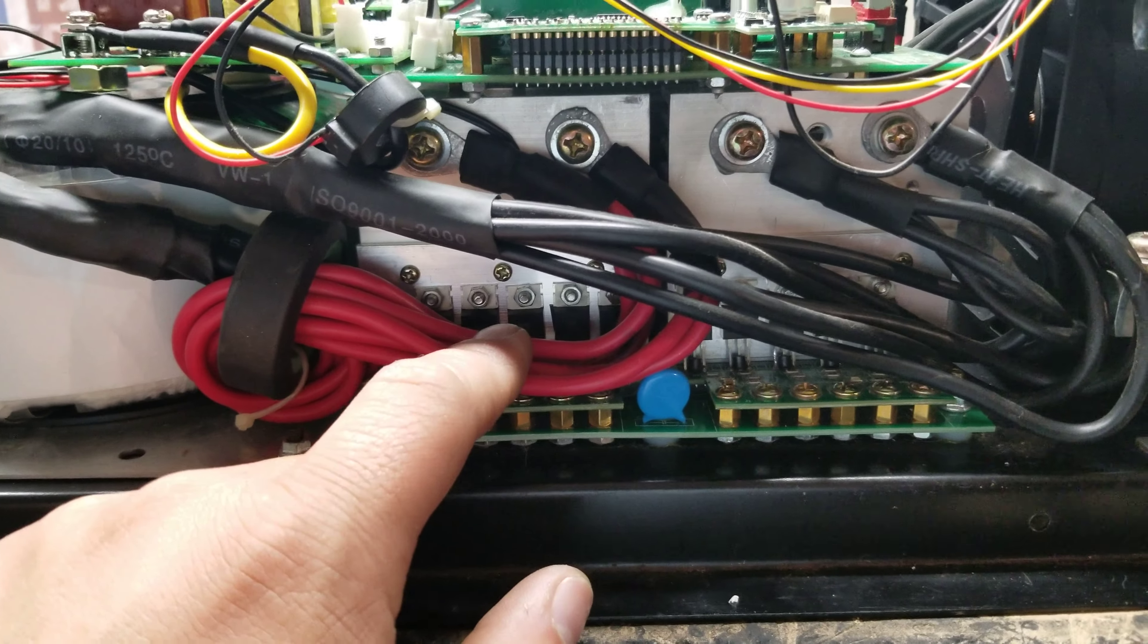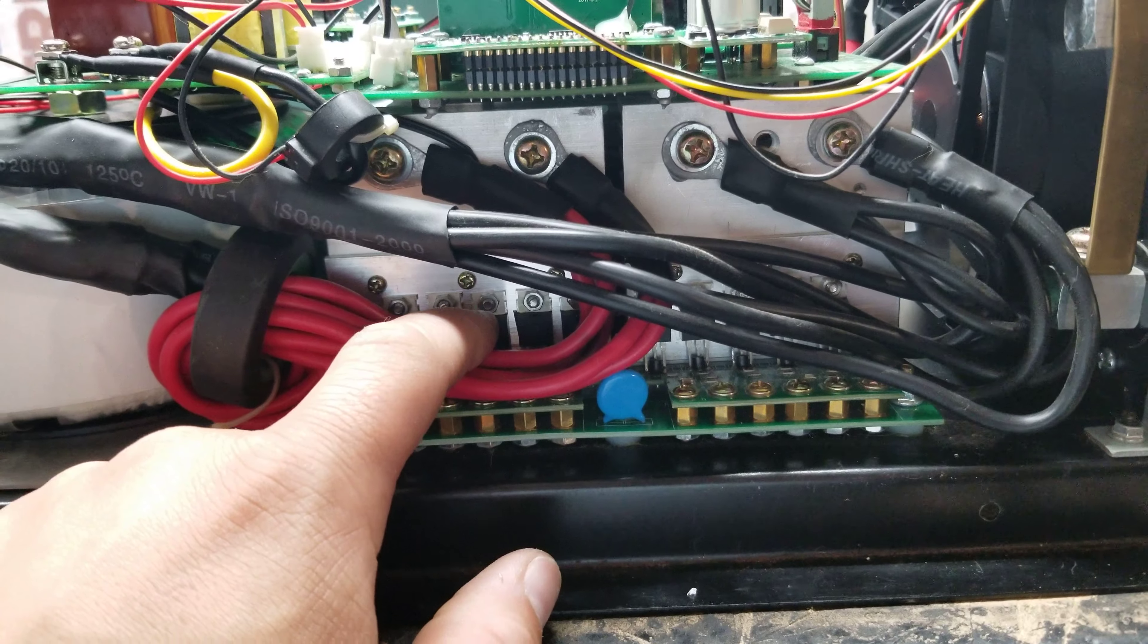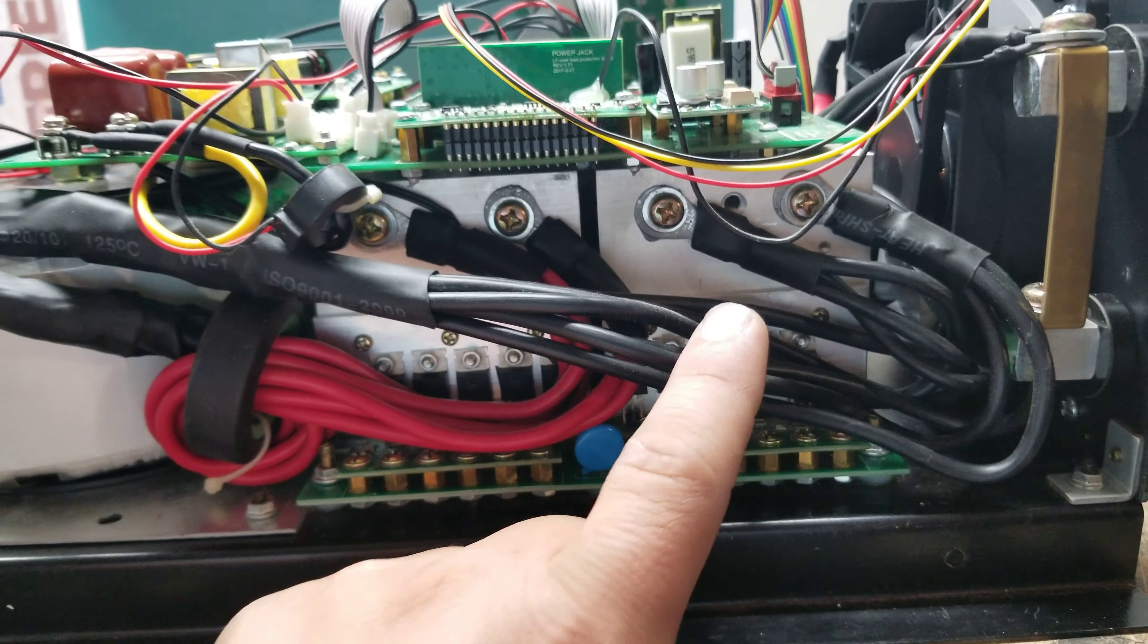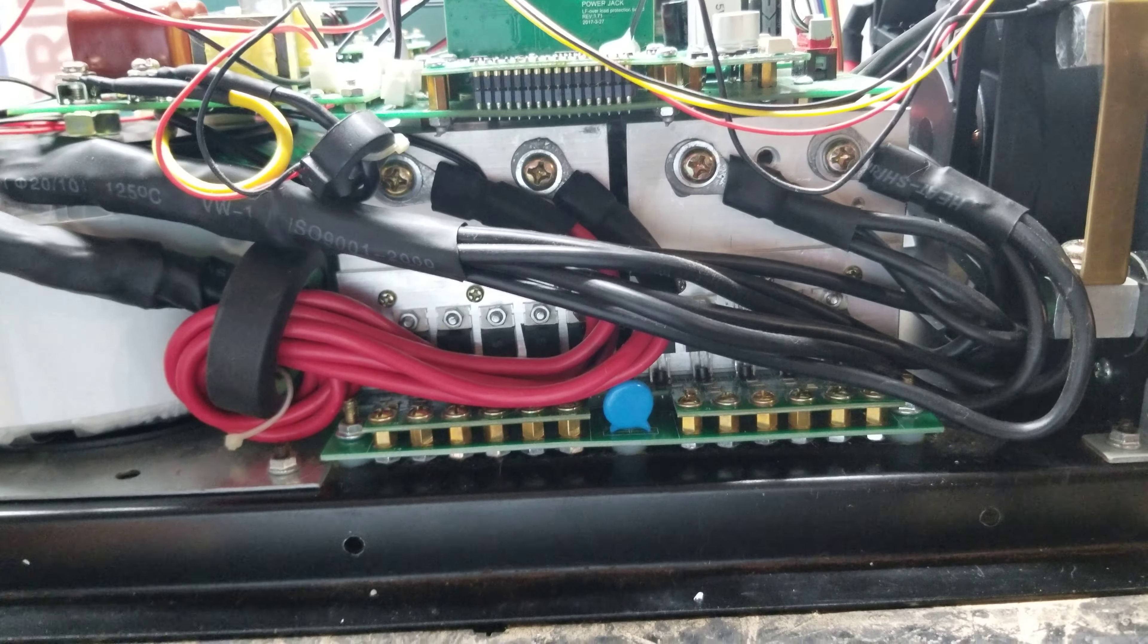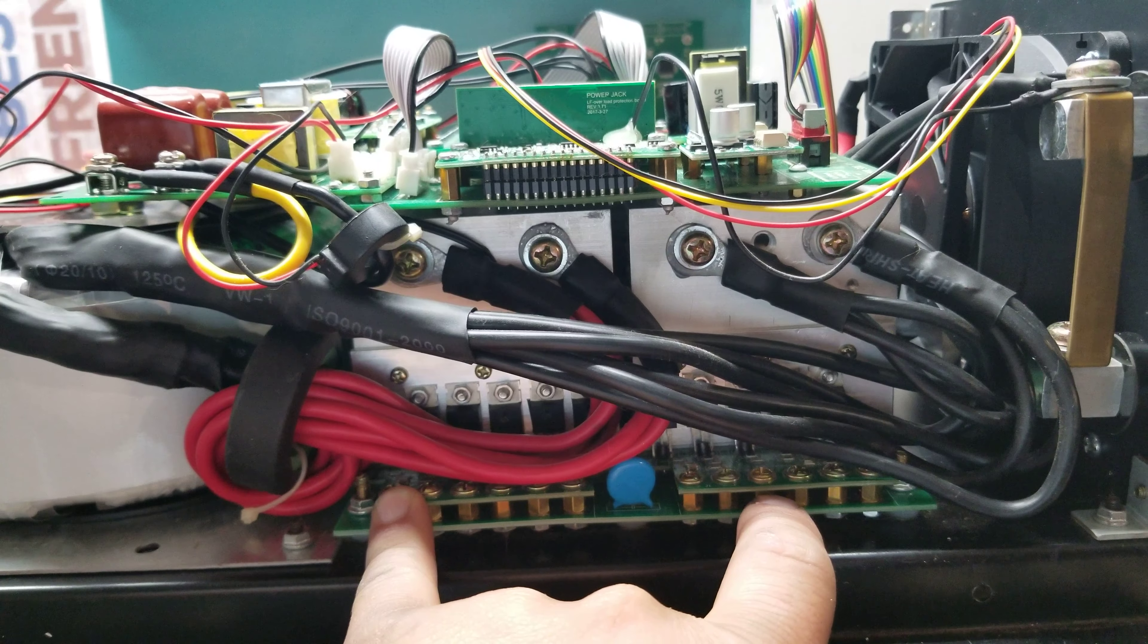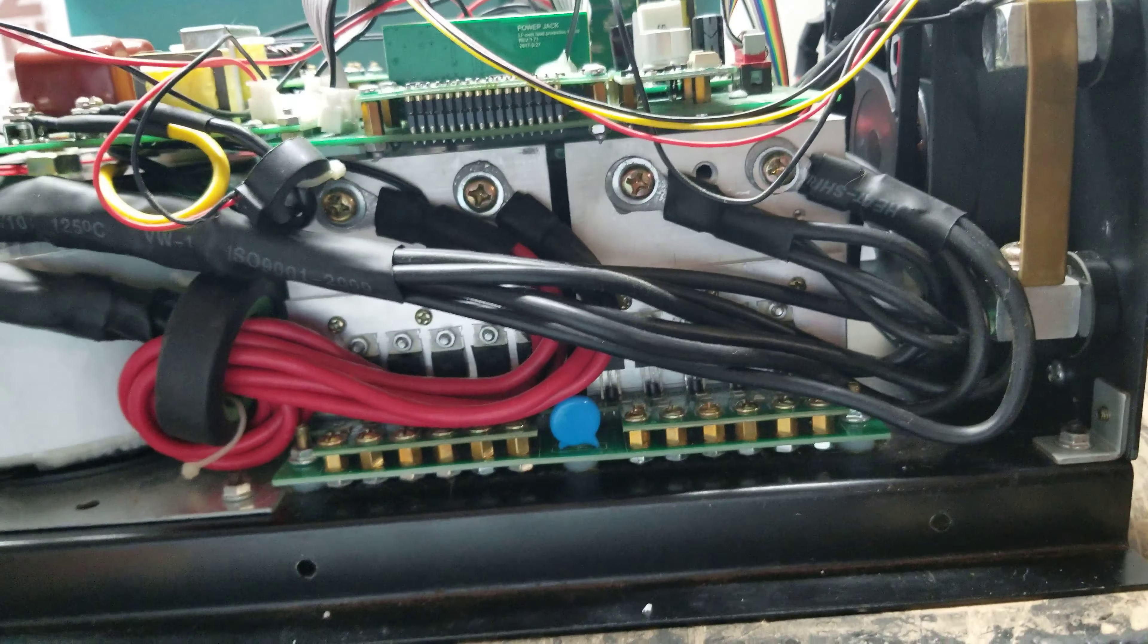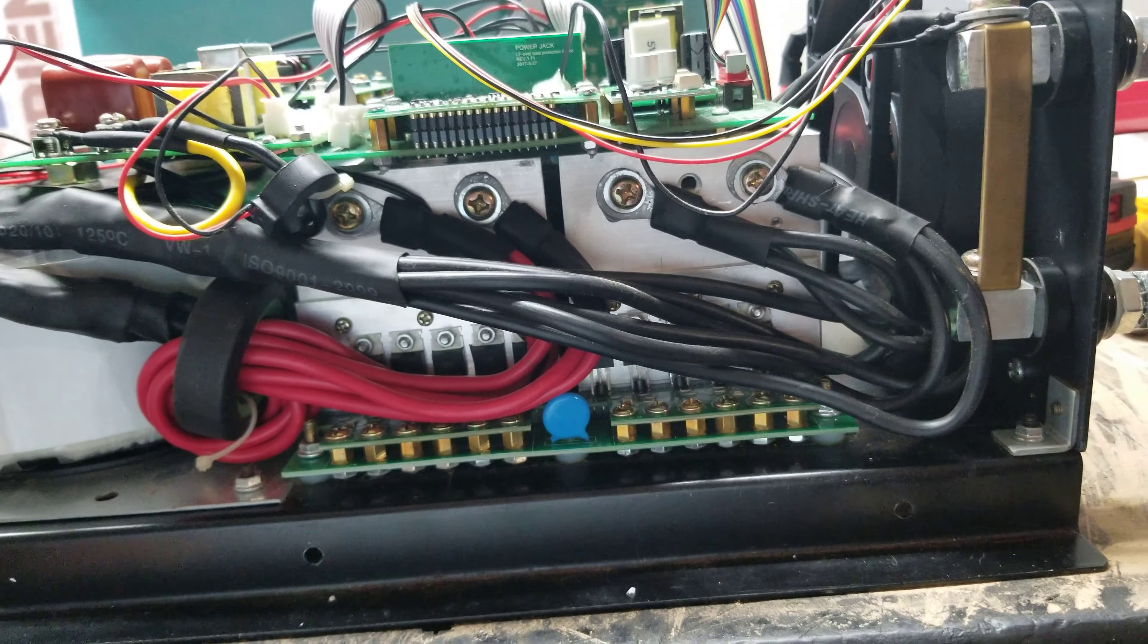These over here actually have a lower ampere rating than the ones on the other side, the newer ones. So these are going to get hotter than the ones on the other side, okay? It's just a good idea to replace all four.